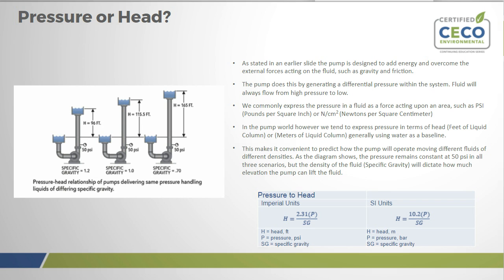In the diagram that you see above, the liquid is pumped to a different height, but the pressure itself, 50 psi in this case, remains the same. So the height difference is all due to the change in density of the fluid itself. As you can see, the equation below is the equation that converts head to pressure. You have the pressure in the equation, but underneath you have the specific gravity of the fluid. So as the density of that fluid changes, the actual head will also change in the system.